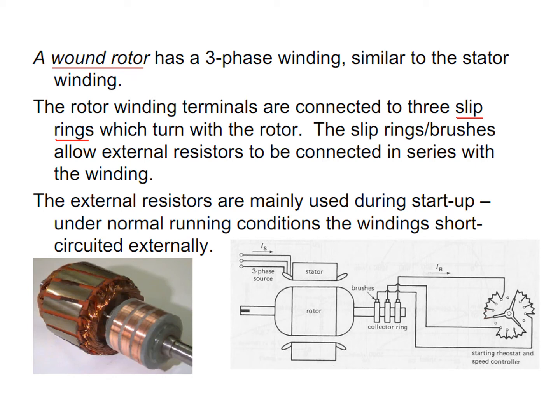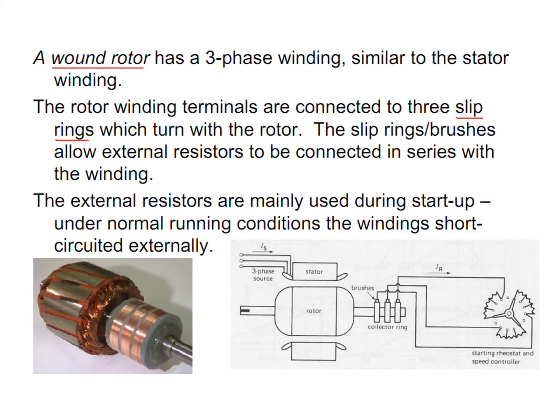External resistances are mainly used during start-up: current flows through resistance and back to the other terminal. After start-up, we short-circuit by rotating the arrangement. This gives flexibility, but it is expensive. So in simple induction motors, squirrel cage rotors are used. This is the complete cutaway diagram of the motor showing the stator windings and the rotor.